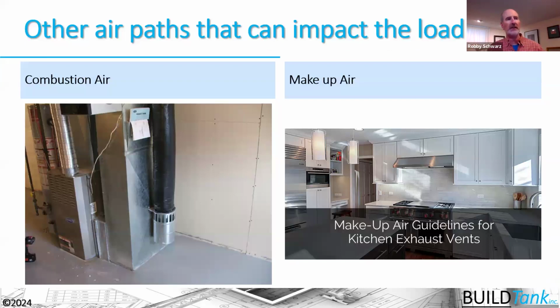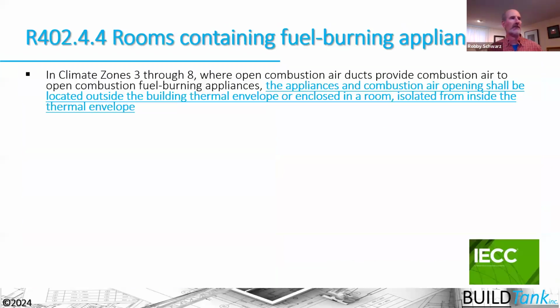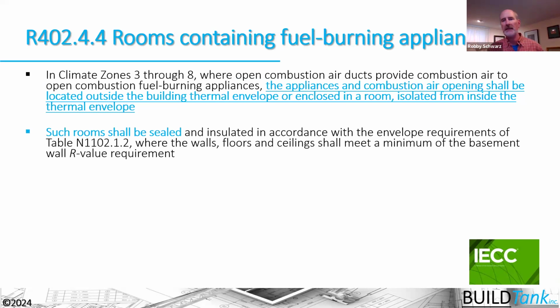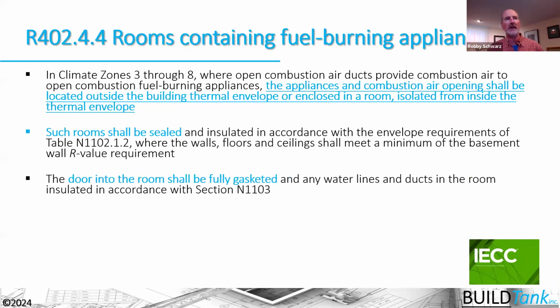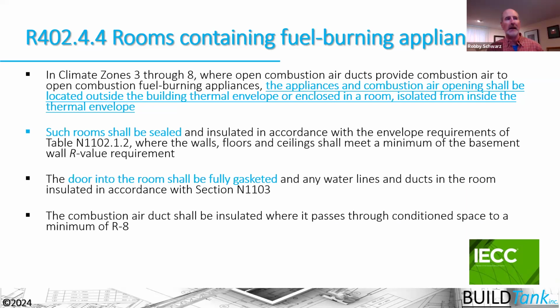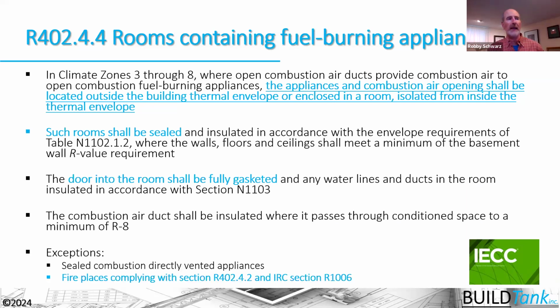With regards to the combustion air on the left-hand side, the codes are trying to address that combustion air and its impact on our houses by saying in section R402.4.4, rooms containing fuel-burning appliances, that these combustion appliance air openings need to be located outside the building thermal envelope or enclosed in a room isolated from inside the building thermal envelope. So basically, these rooms need to be sealed off from the rest of the house as an airtight building, with an airtight building thermal envelope. Those doors to those rooms need to be fully gasketed, weather stripped, and insulated. The combustion air ducts need to be insulated properly. And there are some exceptions for fireplaces and whatnot.